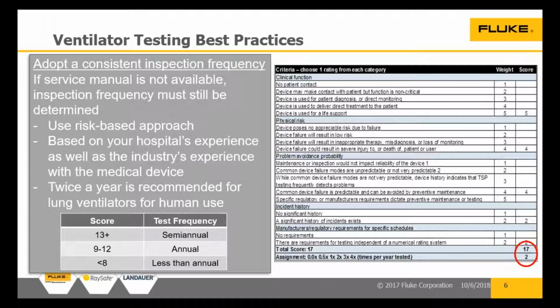So here what we have is a total risk score, when we add all these up, of 17. The criteria says if it's 13 or higher, we need to inspect twice per year, right? Now what we do with that is we compare it to what the manufacturers say for frequency of inspection in their service manual.